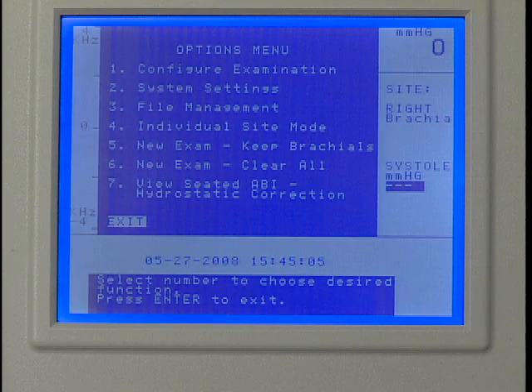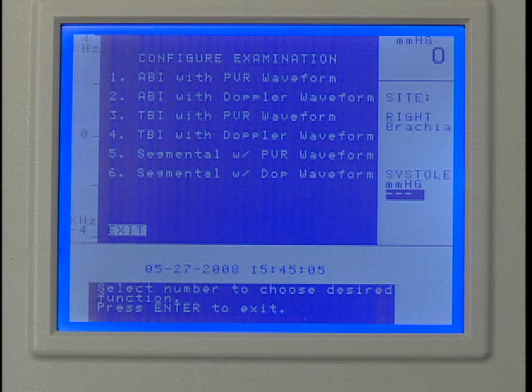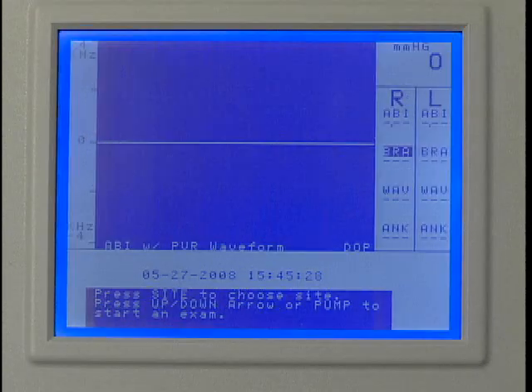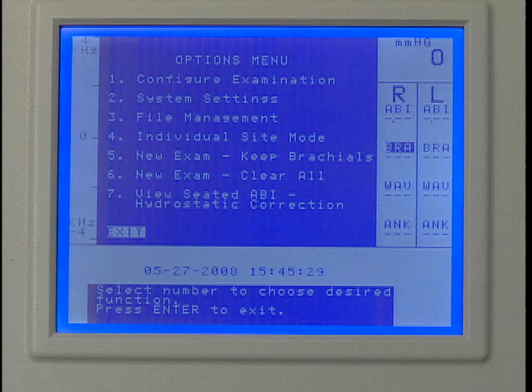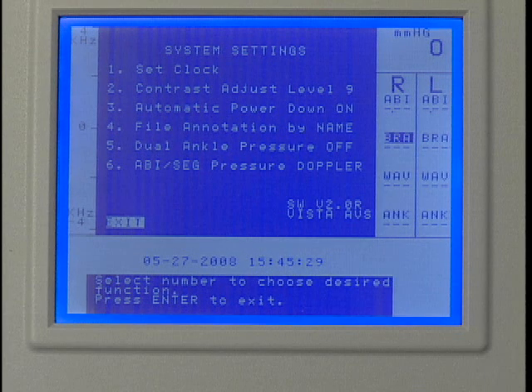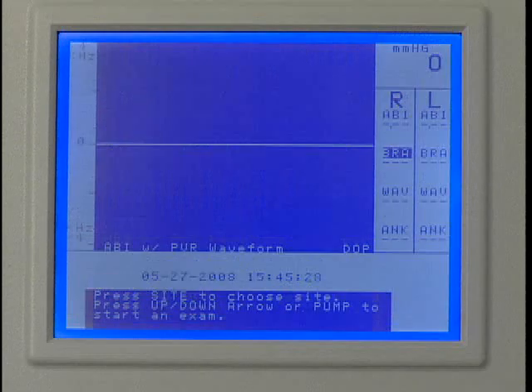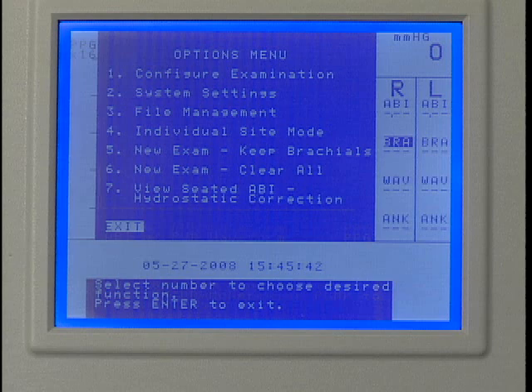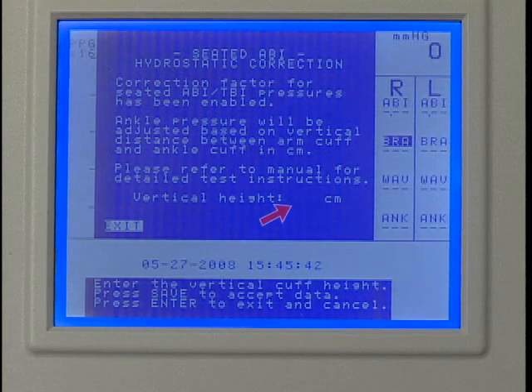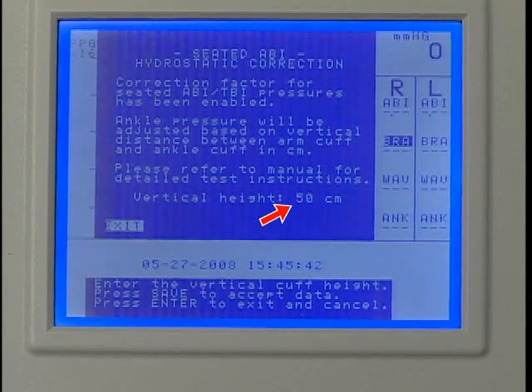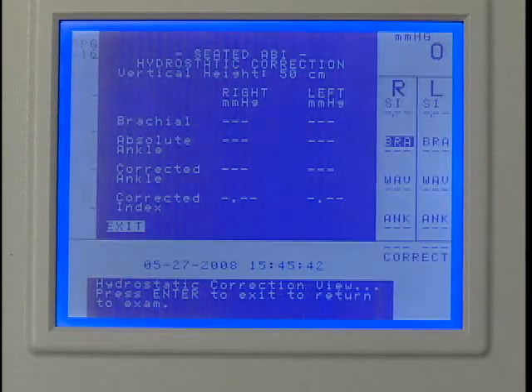Press Enter menu to open the Options menu and press 1 to configure the exam. Press 1 to select ABI with PVR waveform. Press Enter menu to open the Options menu and press 2 for system settings. Press 6 to perform the ABI using the Doppler probe for pressures and then press Enter menu to exit. Press Enter menu to open the Options menu and press 7 for the hydrostatic correction. Enter the vertical distance in centimeters and press Save when finished.